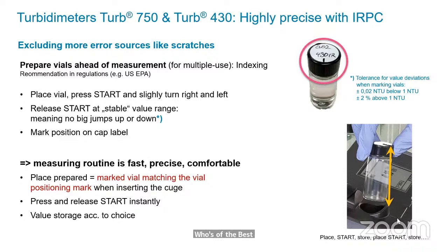And here on the meter, you find a little notch and a little help to align the marking where you have found this place. That's where you mark it. And then you need only place the vial on and on and on in the same position. This makes you quick in routine, and extremely precise. The only thing you have to do if you work with some vials is to prepare them ahead. If you have a single use, so you use it only one time, then you just slightly twist it left and right and see that you do not have the jump.